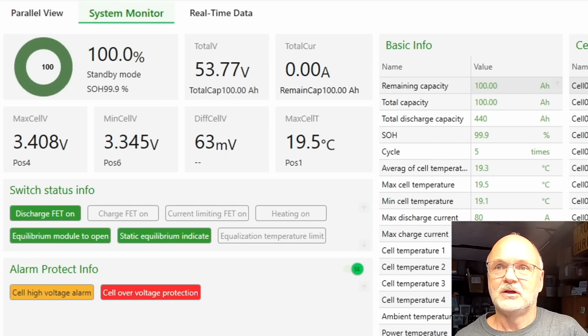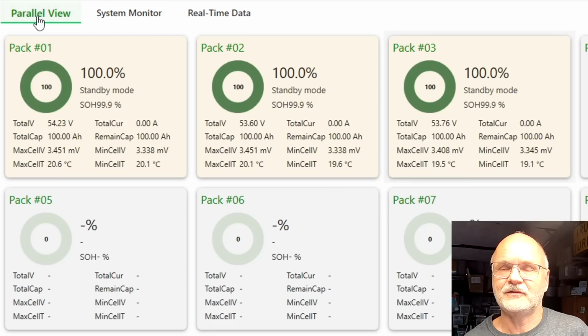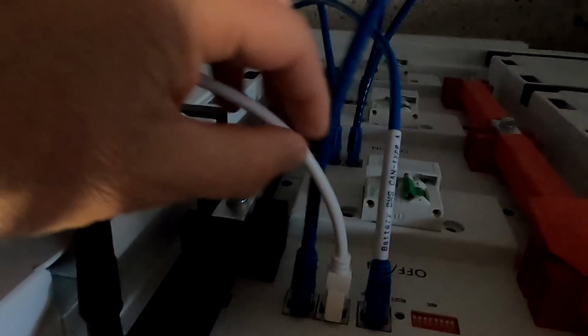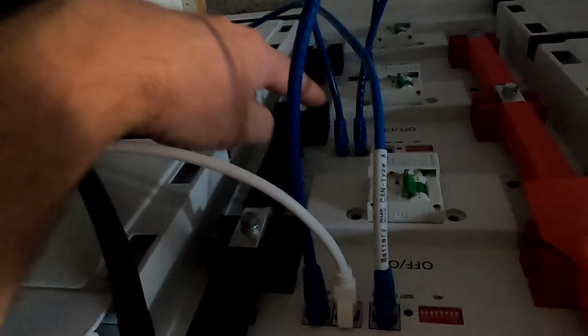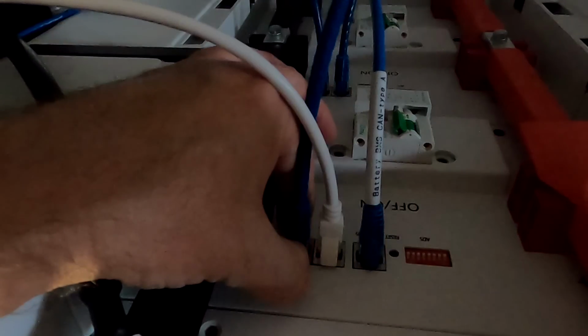So to go into the settings of any of these battery banks, we have to disconnect the LAN cabling at the back, unfortunately. This is my computer cable, this is the cable going to the servo, which is the CAN communication, and this other blue cable goes down to the next battery bank to connect them all together. So you have to disconnect the communication to the other batteries and have only my computer plugged in, and the CAN cable can stay, it doesn't hurt.